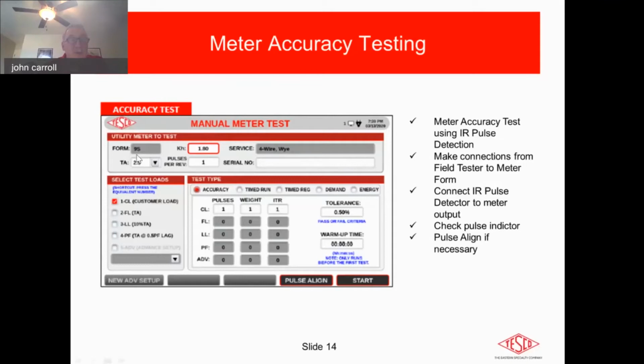In this case, we have a Form 9S. We have the meter constant entered in there already, 1.8 kH. We have the service type, serial number if necessary can go in there, and a whole range of others. We decide on how many pulses per rev we want to set this up for, and the test amps itself.